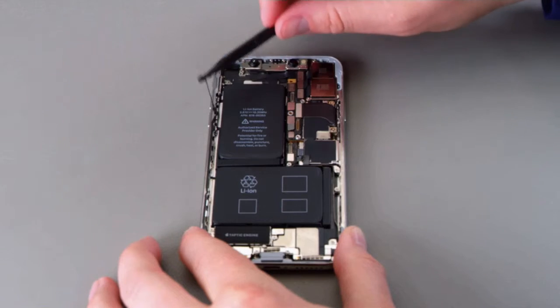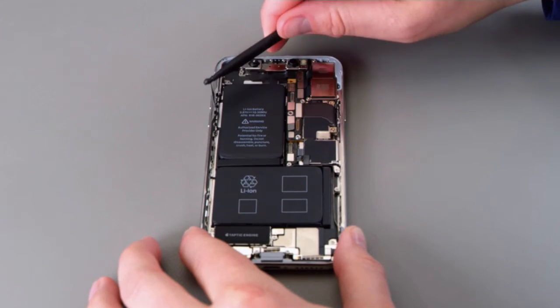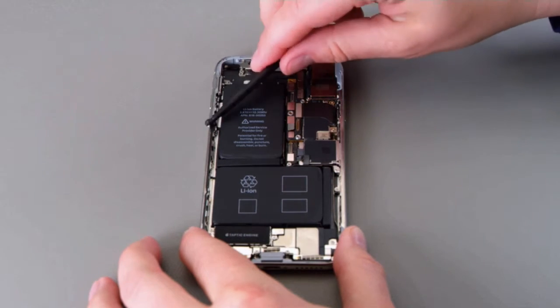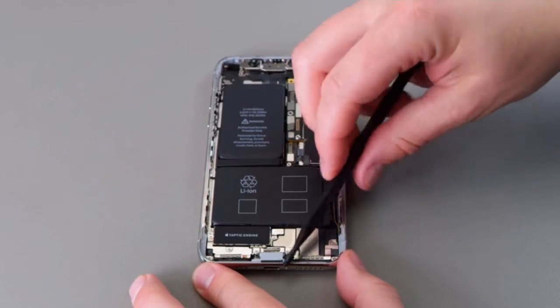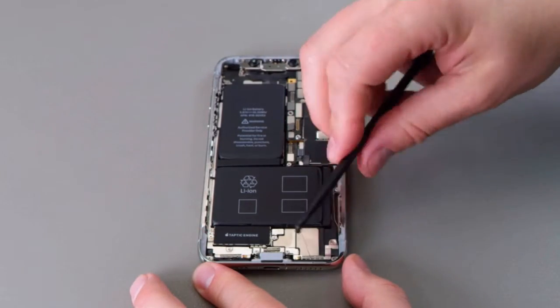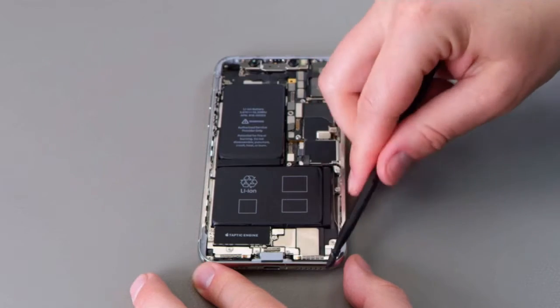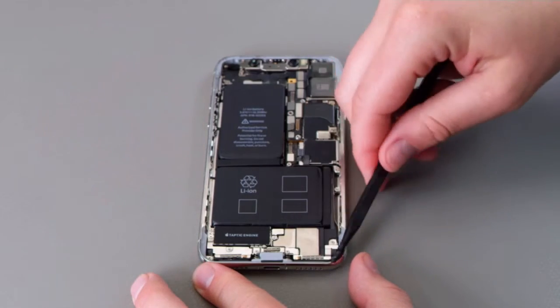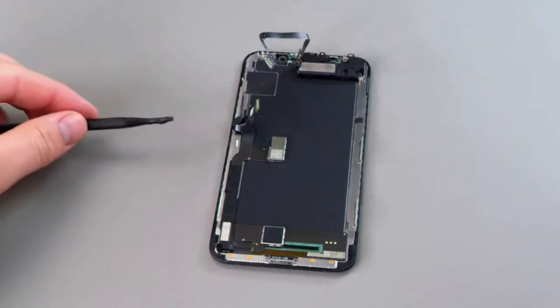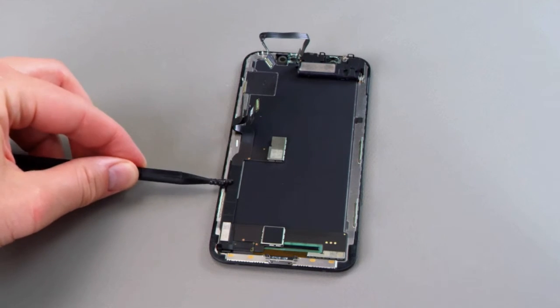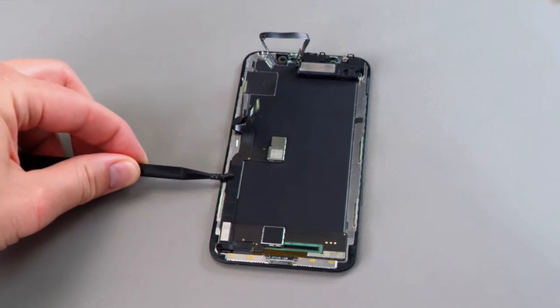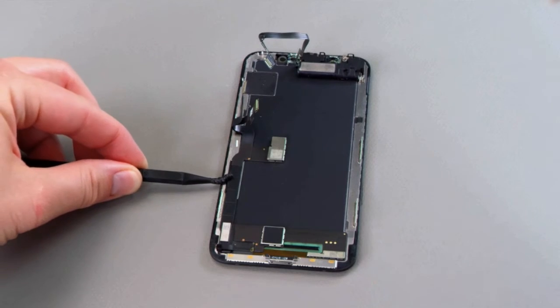Use a black stick to remove the adhesive around the display and enclosure. Don't clean the adhesive off the black stick. It helps lift any remaining adhesive from the enclosure and display. Be careful not to touch the grounding pads on the lower cowling. When removing the adhesive on the display, dab at the adhesive to help pull it up. Avoid scraping or pressing on the back of the display.